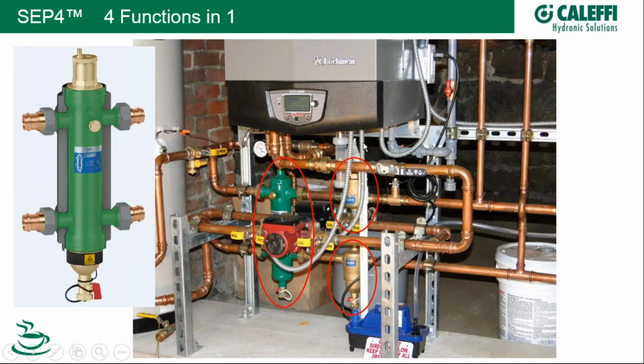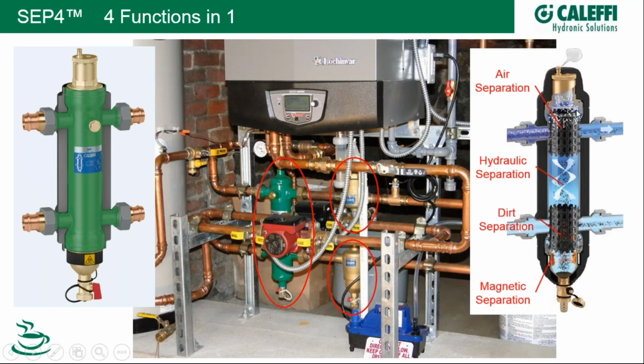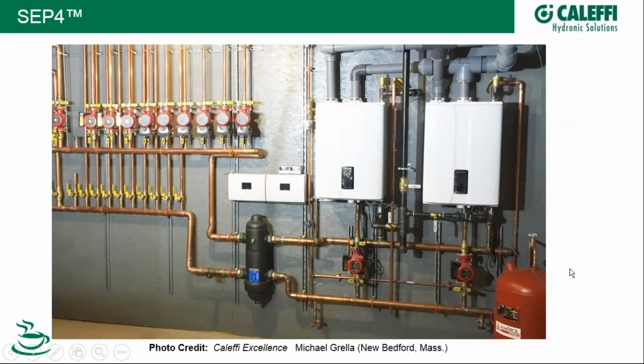And this is a very nicely done job from years ago, before these separators were even available. I imagine if this designer were to do this again, he would save himself a lot of material by simply combining these three, the air separator, dirt separator, and hydraulic separator, into one. And on the inside, they look something like this. Air separation, dirt separation, hydraulic separation, and the added benefit of making sure any corrosion effects get taken care of too, magnetic separation. Here's a job showing a Sep 4 in action, taken from New Bedford, Massachusetts, on the Caleffi Excellence Program.